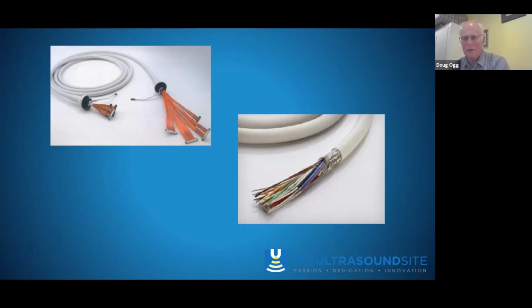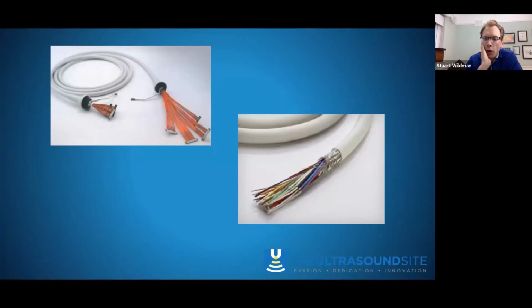And eventually, you can sometimes see it, if you take the probe cable and move it, or when you're scanning and the cable moves, you may see what are sometimes called shooting stars in the image, a kind of comet effect. And that is a clear sign that you've got a damaged cable. And the classic cause, as you say, is running over the cable. They're quite long, aren't they? Unless you have the little hook on the system where you just hook it up and keep it out of the way, it's a classic area where issues can happen like that.